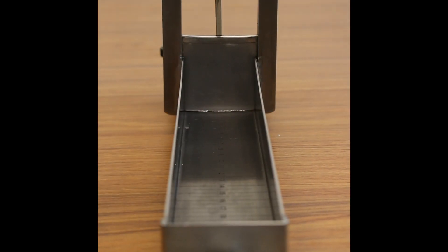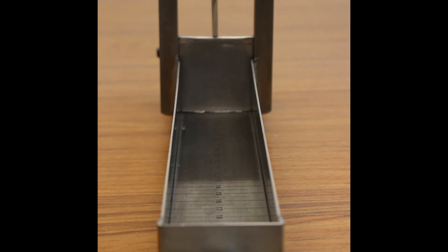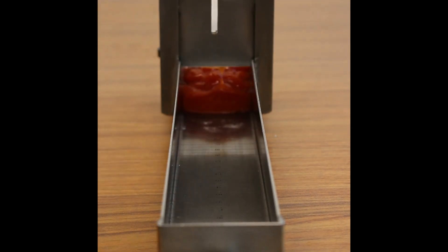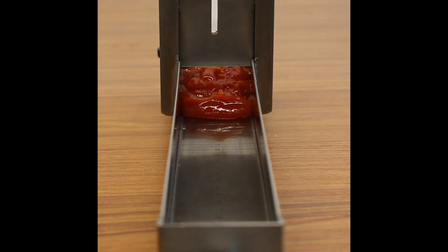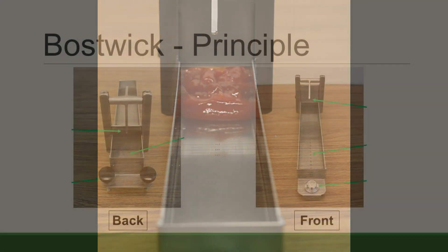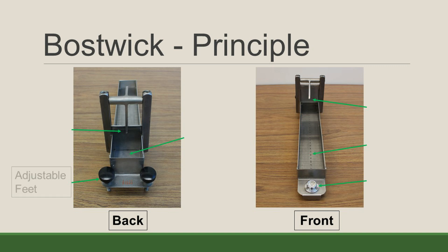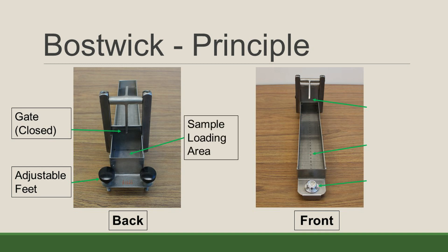The Bostwick is about as basic as it comes. It's a long sloped canal in which you release product and measure how far it flows over a set time to help determine its viscosity. It's commonly used in the tomato and ketchup industry. On the back of the Bostwick you have adjustable feet to change the slope, the gate which is closed in this picture, and the sample loading area.